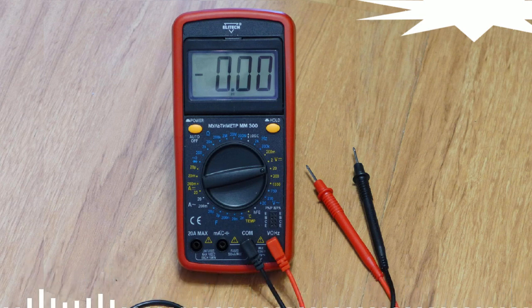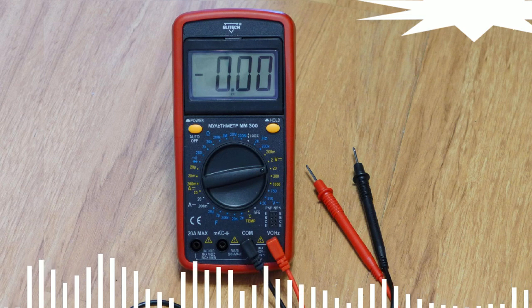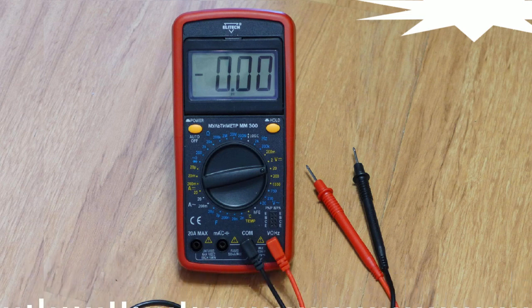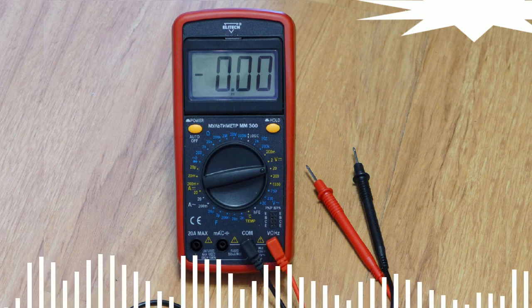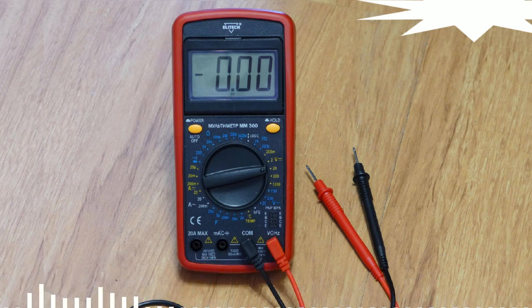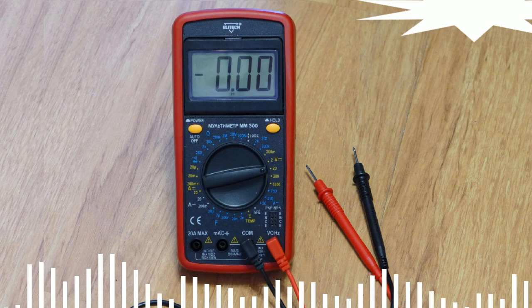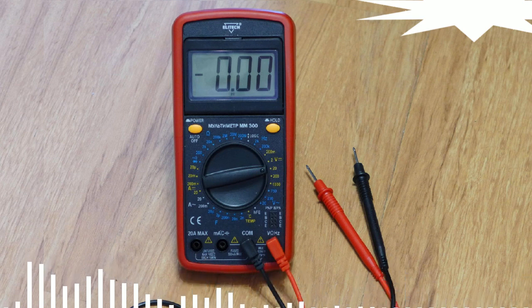Step 2. Connect the wattmeter to the electrical circuit. Connect the current channel to the prepared gap. Connect the voltage channel to the output switching device using wires. Apply voltage to the circuit. Determine the value of the power consumption on the indicator of the device and record the obtained value as the result of measurement by the direct method, P1.